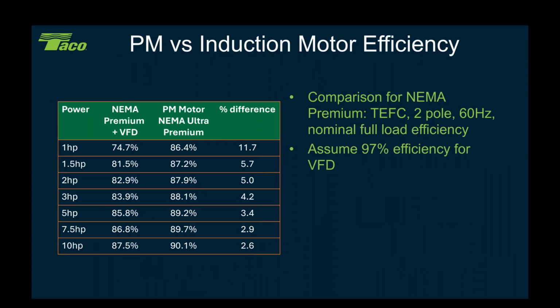Okay, so we have to start thinking about where this makes sense in our industry. They make permanent magnet motors up to, I think the biggest one I've seen so far is 100 horsepower. They are real common in the smaller horsepower ranges, and part of the reason they are more common in the smaller horsepower ranges is that they are more efficient than either NEMA Premium or NEMA Ultra Premium motors. Okay, if you look at a 1 horsepower permanent magnet motor, it's almost 12% more efficient than a conventional ultra premium motor.